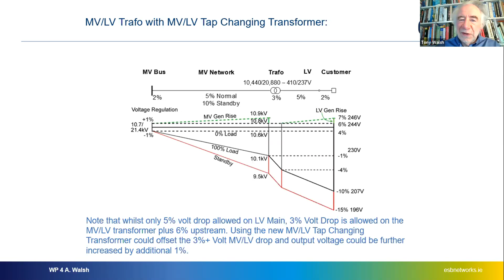If you put extra electric vehicles and so on, that voltage drop might be exceeded. However, if we use a tap changing transformer, we can jump the voltage on the output up to 244 volts. And now we've added another 20 volts. We've nearly doubled the voltage drop that we can allow before there's a problem. So this is quite a clever approach.